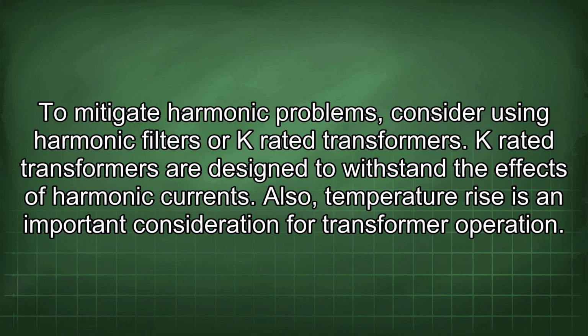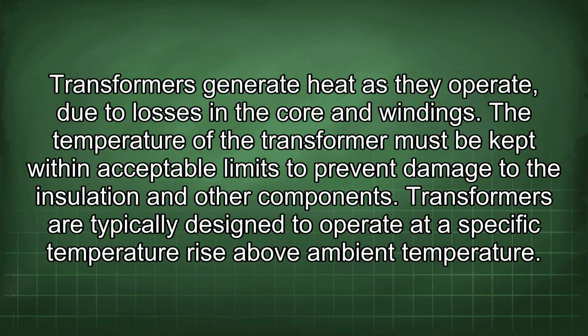Also, temperature rise is an important consideration for transformer operation. Transformers generate heat as they operate due to losses in the core and in the windings. The temperature of the transformer must be kept within acceptable limits to prevent damage to the insulation and other components.